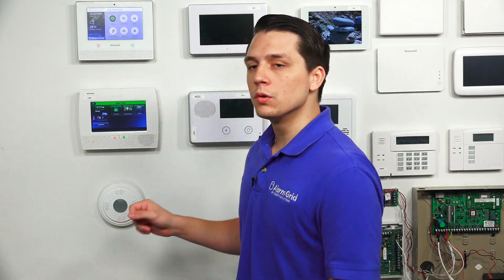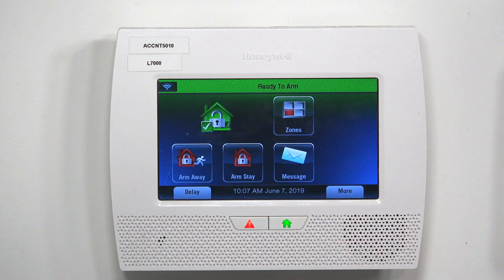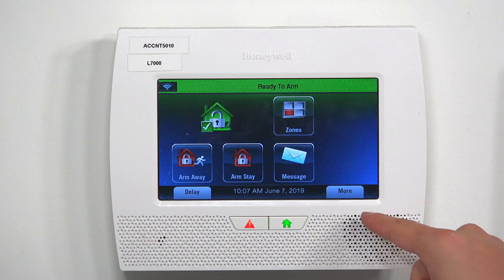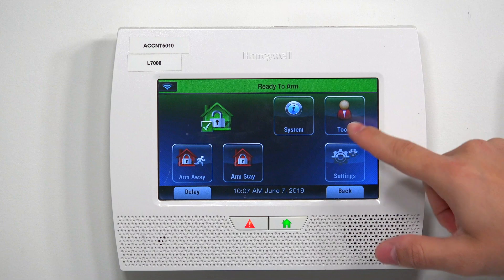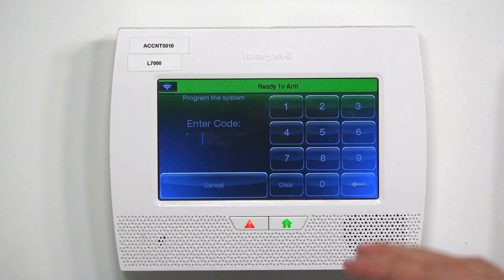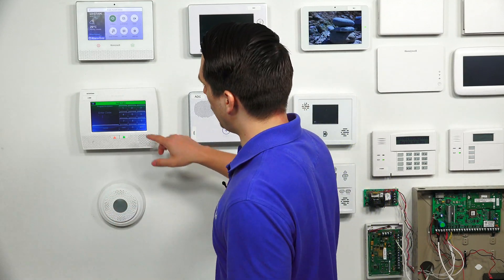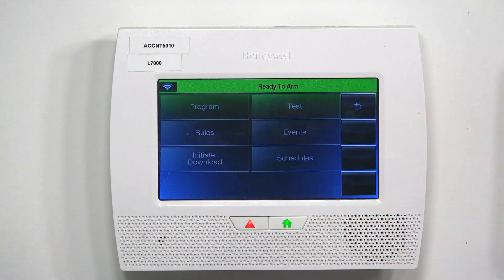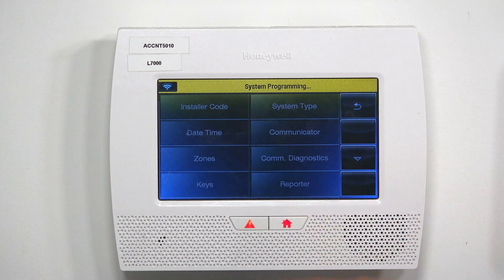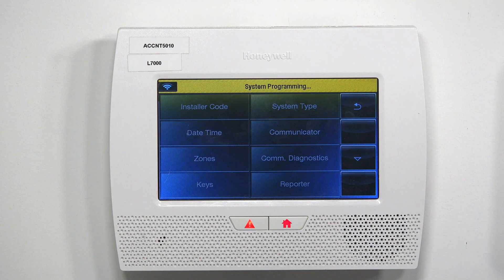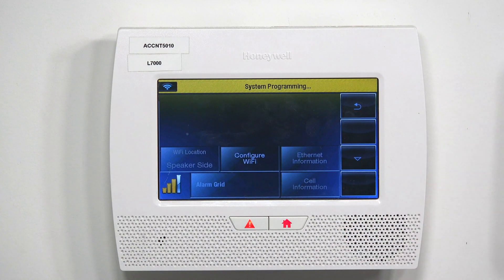At the main screen, press Security. Then at the bottom right, you're going to see an option for More. Then tap Tools. It's going to ask you for a code, so you're going to type in the installer code. The default installer code for the system is 4112. Once you're in, press Program, and then look on the right side for Comm Diagnostics and tap on that.